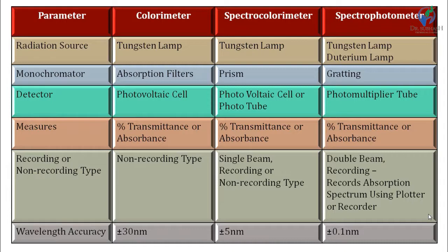Now we will see the basic differences between these three instruments. The four basic components are: radiation source, filter or monochromator, sample holder, and detector. In colorimeter and spectro-colorimeter, tungsten lamp is used as radiation source. In spectrophotometer, two sources are used: tungsten lamp and deuterium lamp. For the monochromator, colorimeters use absorption filters, spectro-colorimeters use a prism, and spectrophotometers use a grating. Efficiency increases in the order: filters, then prism, then grating.